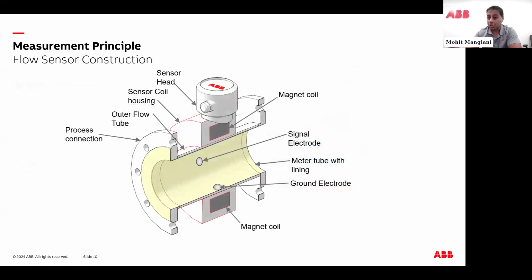In terms of terminology, just to go over details when somebody's talking to you or trying to explain something to you, or if you have questions. Process connection is always the connection that's touching mating piping. We have our outer flow tube, which is basically a housing, and I'm going to get into more detail there. You have a sensor coil housing on the outside that shields and protects all the electrical on the inside. You have a sensor head on the top of this device. Basically, all the analog measurements happening down here come up into a board in the top of the head, and this is what your transmitter is typically interfacing with.